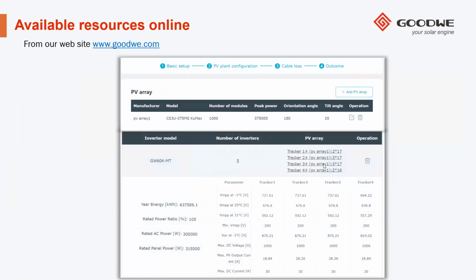We have a large amount of modules already pre-configured onto our portal, but you can also input custom modules as well. The nice thing about this is you select your location of the plant and it calculates the geometrical data. It takes the lowest average temperatures as well as the highest average temperatures and calculates your temperature coefficient to ensure that your PV voltage will not exceed the rated current and voltage of your inverters. And this is something very important that a lot of installers don't always have access to. You'll see it gives our VMPP, our VOC, and the max DC currents as well.